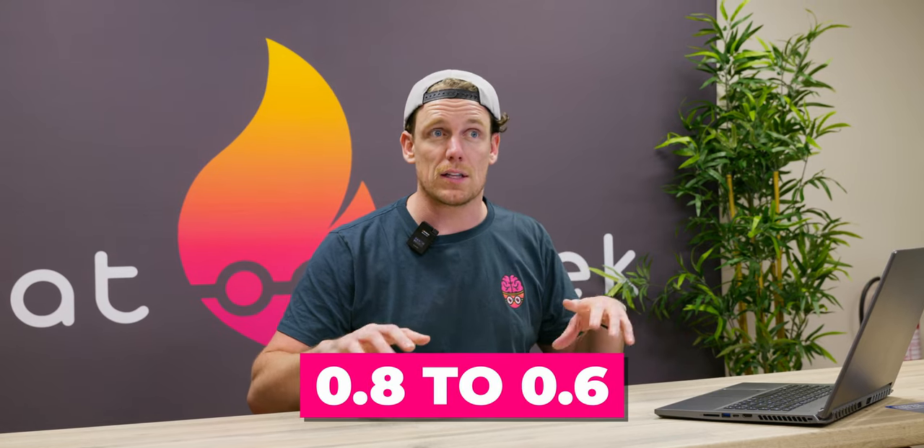It's getting to the time where opinions need to be updated to account for good system design and modern heat pump efficiencies, which have increased. The two additional changes we made were changing our weather compensation from 0.8 to 0.6, and adjusting some balancing, which can improve SCOP and efficiency in some scenarios — we will make a video on that, so make sure you subscribe and hit the bell notification. It's also worth noting our heat pump is particularly good with particularly good controls, and it's not doing hot water; if you were to add hot water it would probably shave about 0.25 off these COP figures.